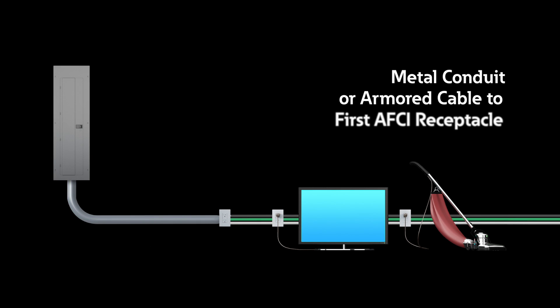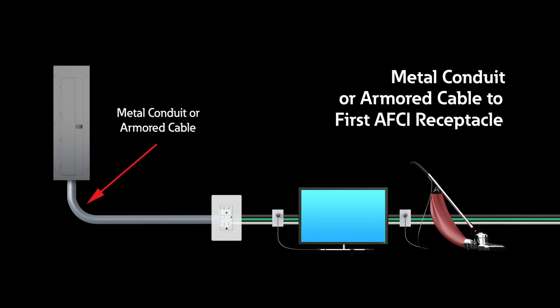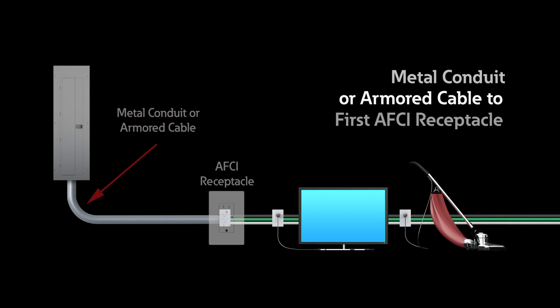Metal conduit or armored cable to the first AFCI receptacle. This installation requires metal conduit from the panel to the first AFCI receptacle in a circuit. This allows for local reset capabilities, but installation of conduit can be costly and impractical in many applications. However, this may be the most practical application for dormitories, hotels, or other commercial applications.